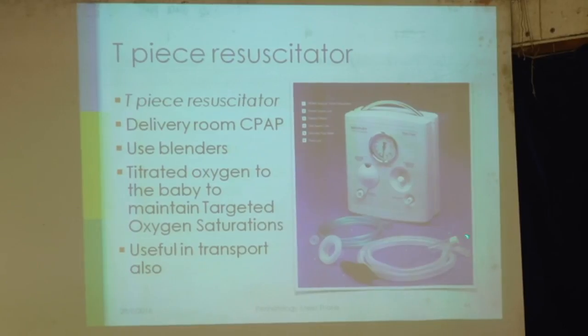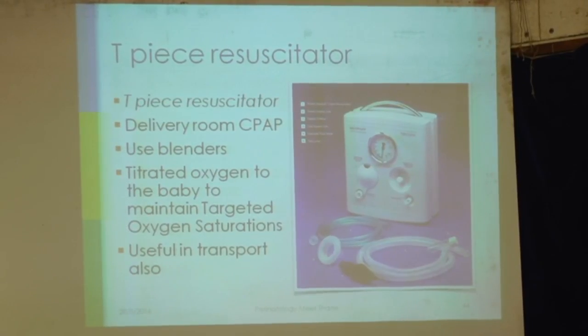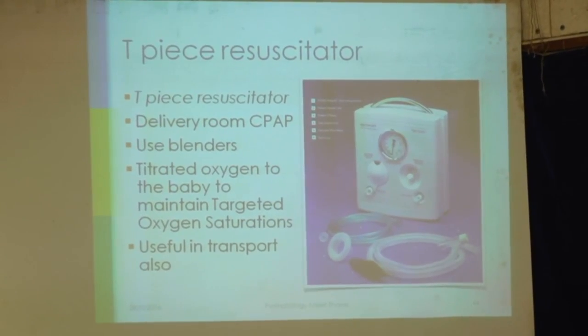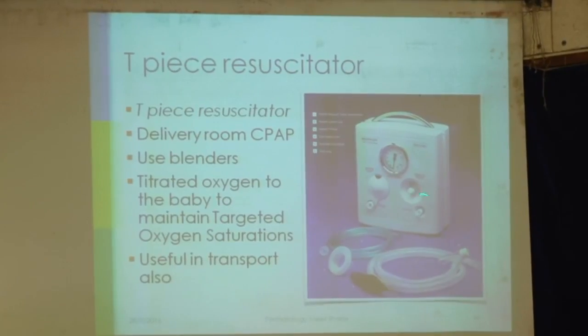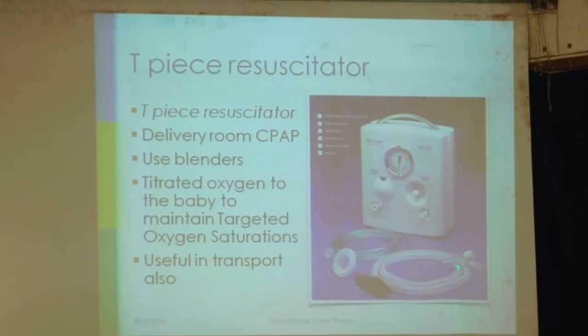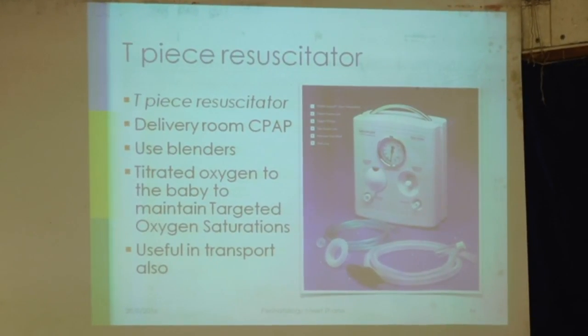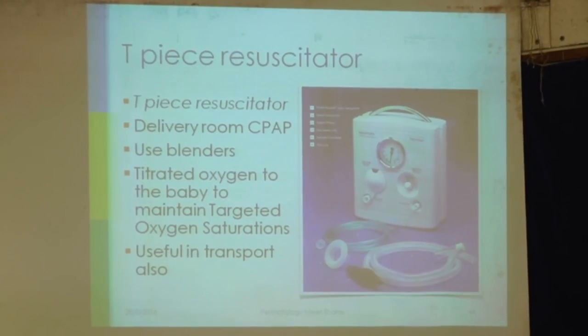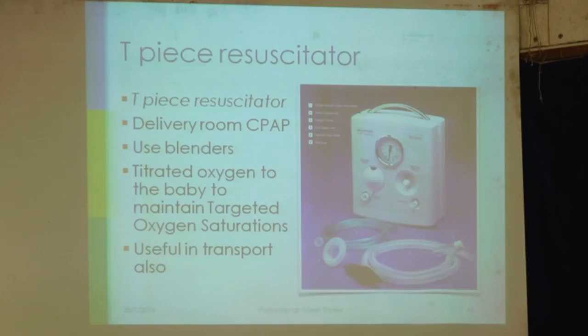Now there is a white circle here which is the regulator for the PEEP, the end expiratory pressure. So the PIP is set from here, PEEP is set from here. We set the PIP, close the ET end of the tube with our palm, and then you will see the positive pressure generated. Once you release the thumb pressure, that will give you the PEEP. So in case the ET is there and this tube is connected, continuous CPAP will be delivered to the baby. Depending on the baby's condition, we can set PIP from say 15 to 25 as per the requirement, and PEEP is usually set at 5 or 6. So this will give a continuous uniform PIP as well as PEEP.